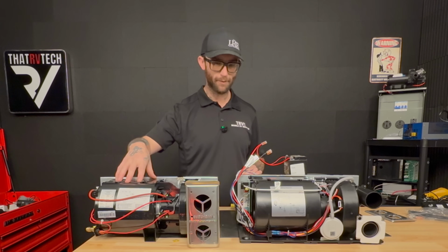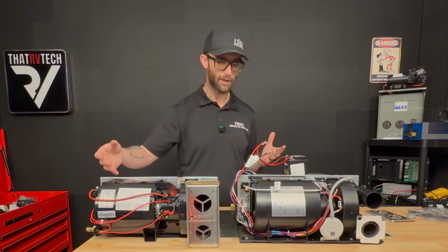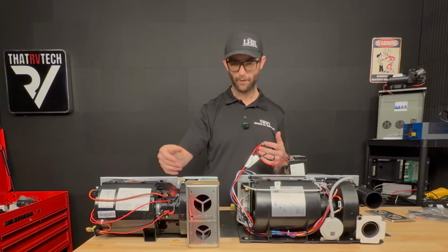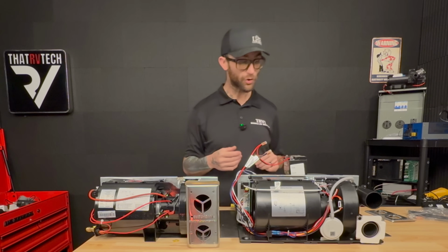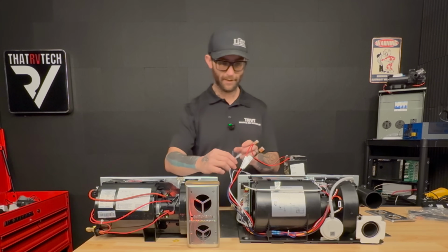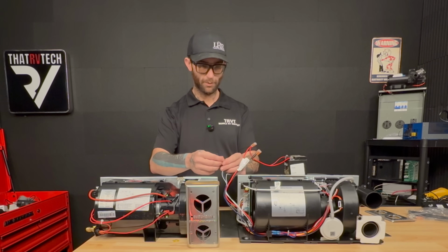Because when you add power to these, there's no relay. The relay only closes when you ask for the fan to come on. This one is clicking as soon as it gets power. But let's get these blue wires here twisted.